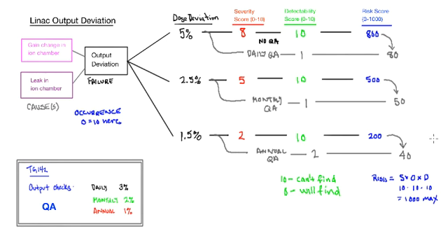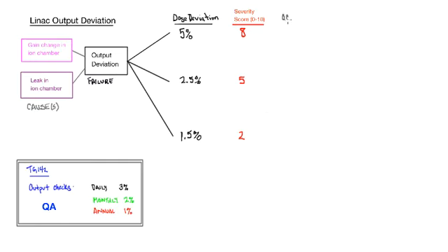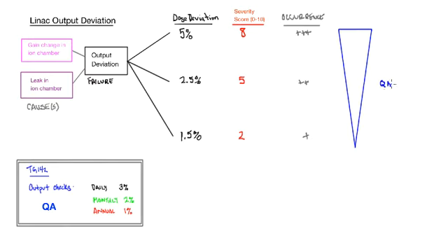So let me just summarize that by looking at this in a slightly different way. So we have severe things, and then we also have very frequently occurring things, and it's one or the other or both, so medium, high, and low. And the QA needs are different. The QA needs will be driven by a combination of severity and occurrence, or the risk. So basically more QA needed as you go up in either occurrence or severity. What does that mean, more QA? It could mean more frequent tests. That's the simplest version of that, and that's what we saw.